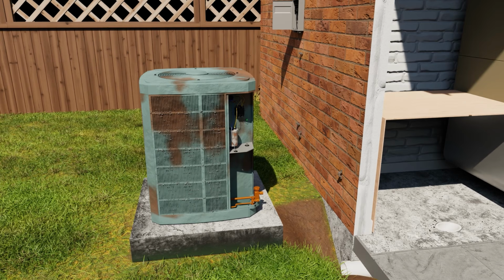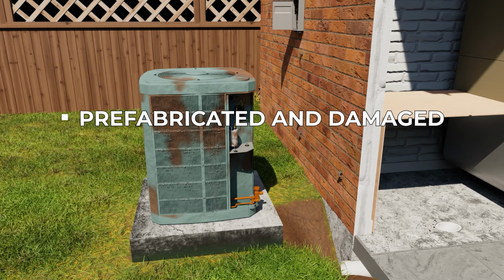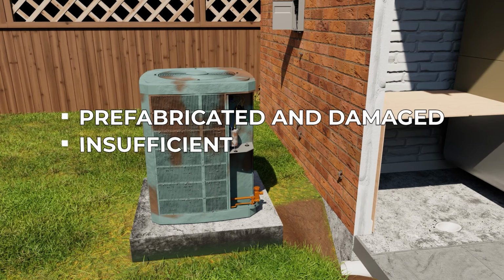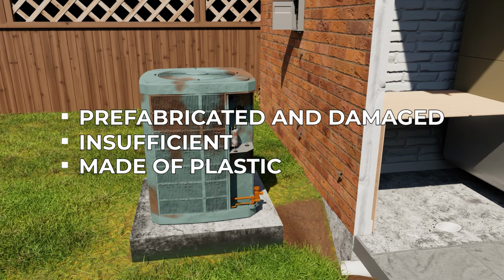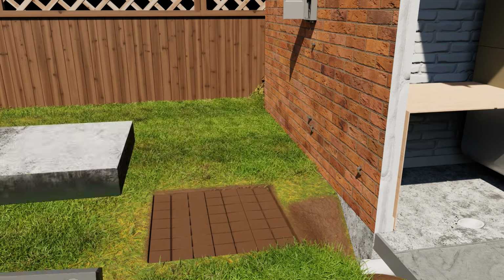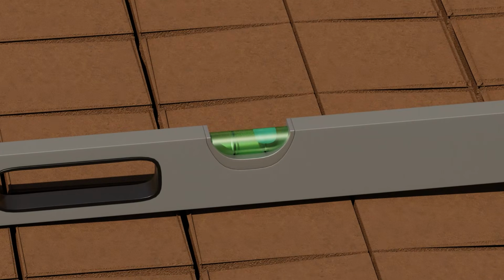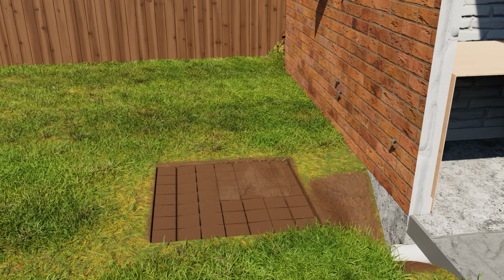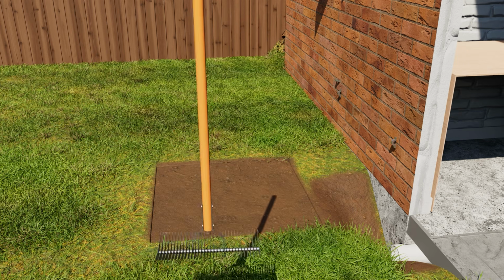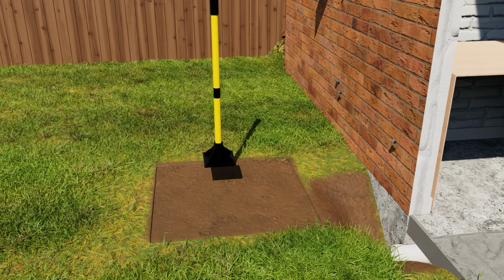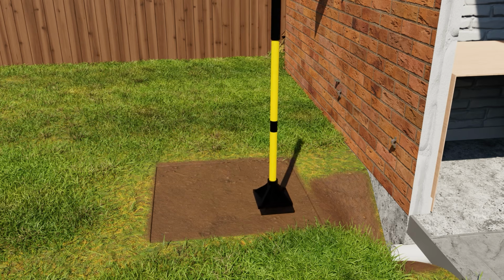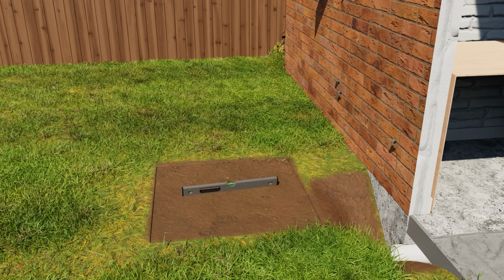We would often do this if the existing pad was prefabricated and damaged, if the existing pad was insufficient in some way, maybe well below grade, or if the existing pad was made of plastic. Here we show a good procedure, if not maybe a little bit overkill, for leveling the pad. First using a level, then moving some dirt around to improve the leveling of it. A rake and a tamp can be used to create a nice firm foundation. Then use the level to determine that we're level in all directions.